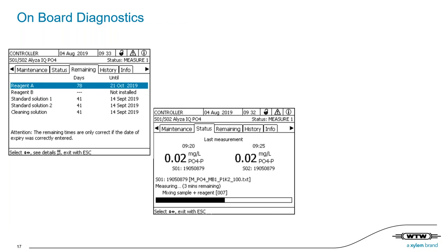Okay, next question. What would you recommend as the calibration frequency for the Alyza? So what I mentioned, the exchange every 12 months of the reagent and the standard, the cleaning solution and the standard solution is a daily calibration. So that's what we recommend. Cleaning once per day, calibration once per day, that's it. And as I mentioned, you have the option of a 1 or 2 point calibration.